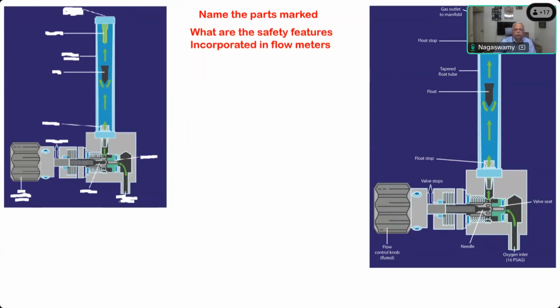Okay. What are the safety features incorporated in flow meters? So they're color coded, touch sensitive. They're fluorescent, and the color-coded knobs illuminate in the dark. Okay, the tubes are not color-coded. These are the knobs which you control to open and close. They are color-coded. They are different fluted. They are different to touch. Oxygen is the biggest fluted knob. The others are all small fluted.